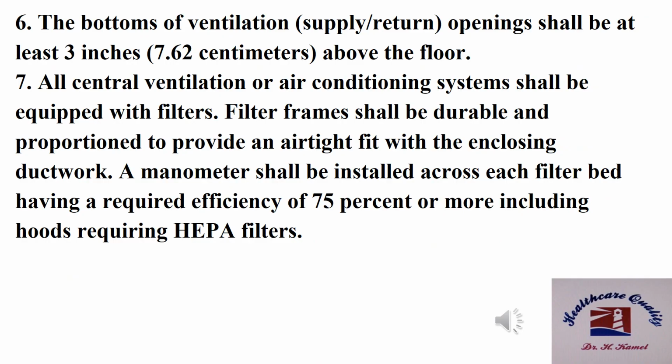Number 6, the bottoms of ventilation openings shall be at least 7.6 centimeters above the floor. Number 7, all central ventilation or air conditioning systems shall be equipped with filters. Filter frames shall be durable and proportioned to provide an airtight fit with the enclosing ductwork.